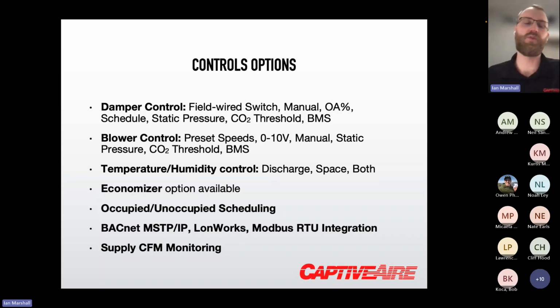For controls, we can manage anything on the controls side. We manufacture all of our controls in-house. We have some flexibility in that regard. Depending on the job and the sequence of operation and the requirements, we're pretty flexible on what we can make work. We have the capability to modulate damper and blower with field wires, switch, preset speeds or positions, manual control. We can take 0 to 10 volt inputs. We can do static pressure controls or CO2 controls. For temp and humidity, we can do a discharge. We can do a space control.